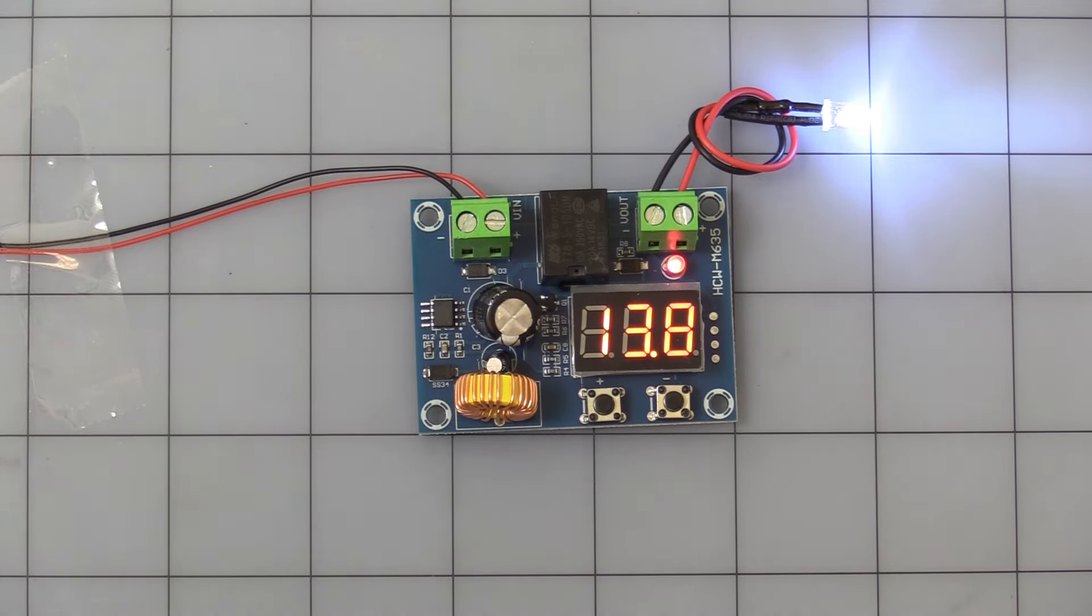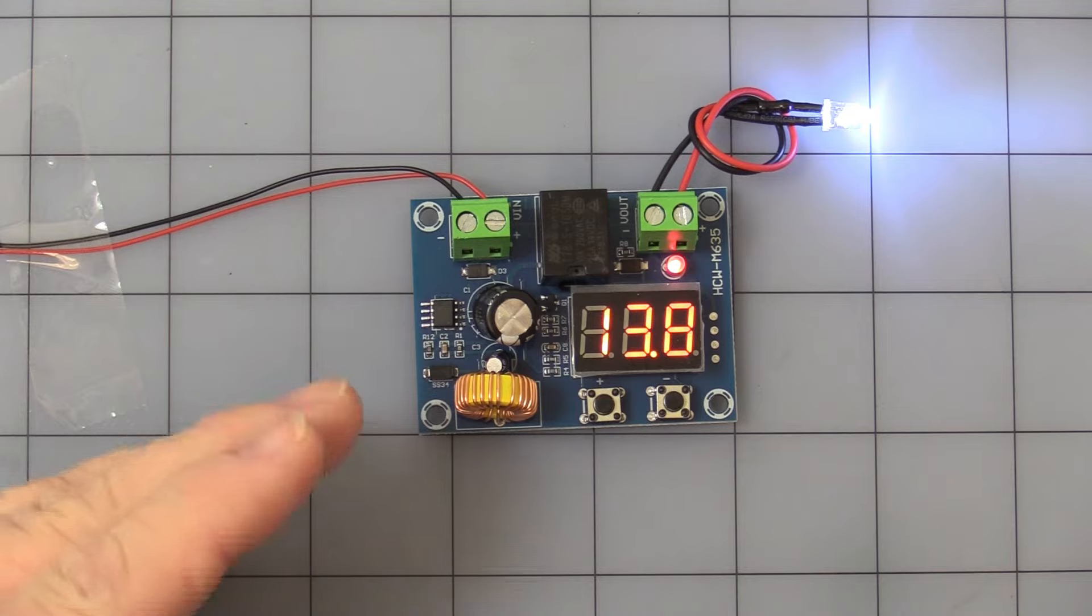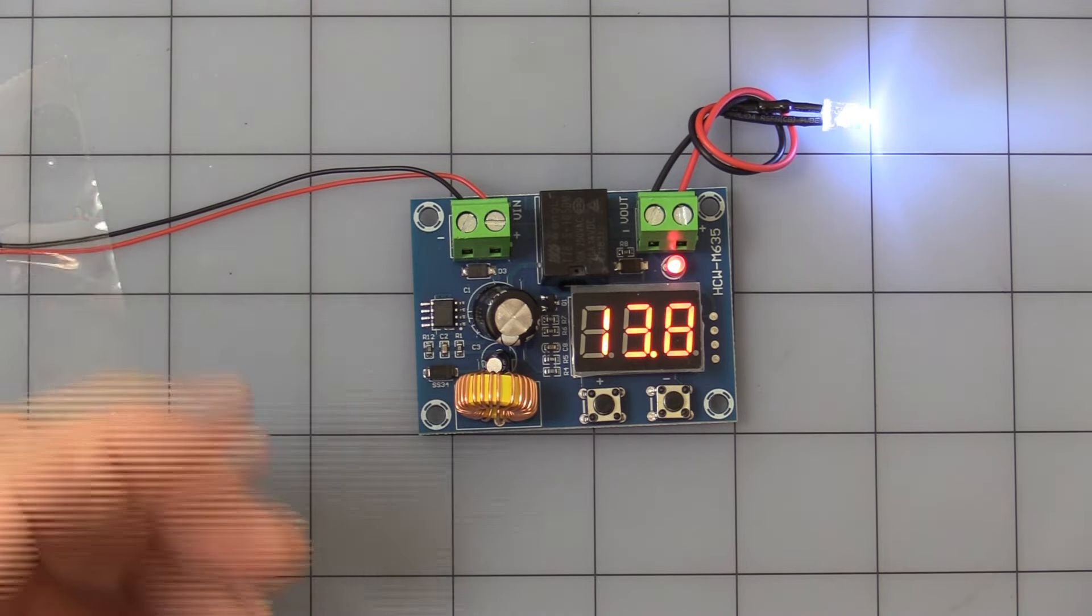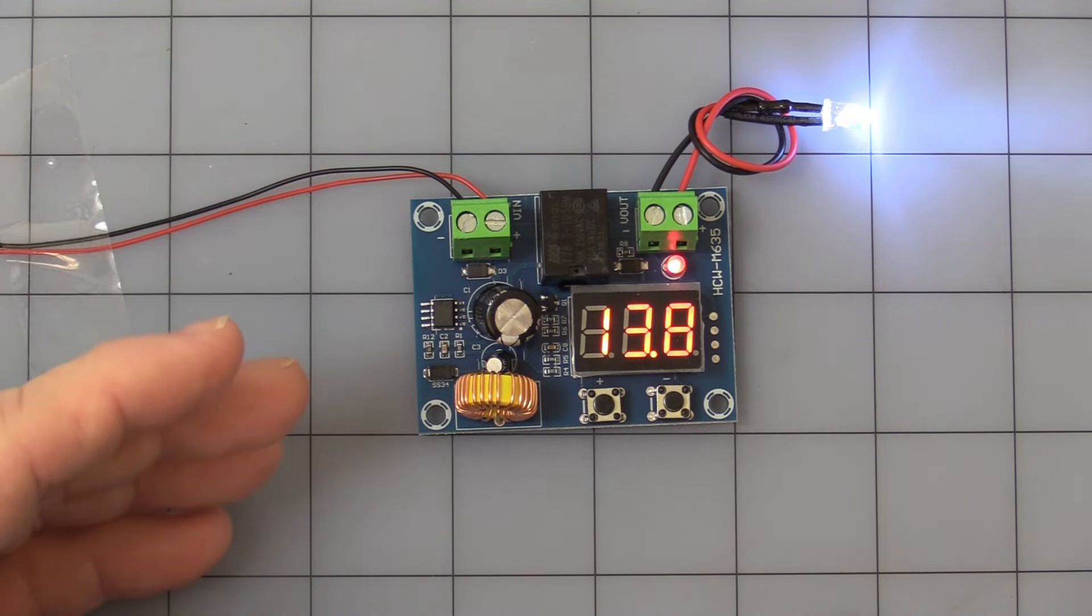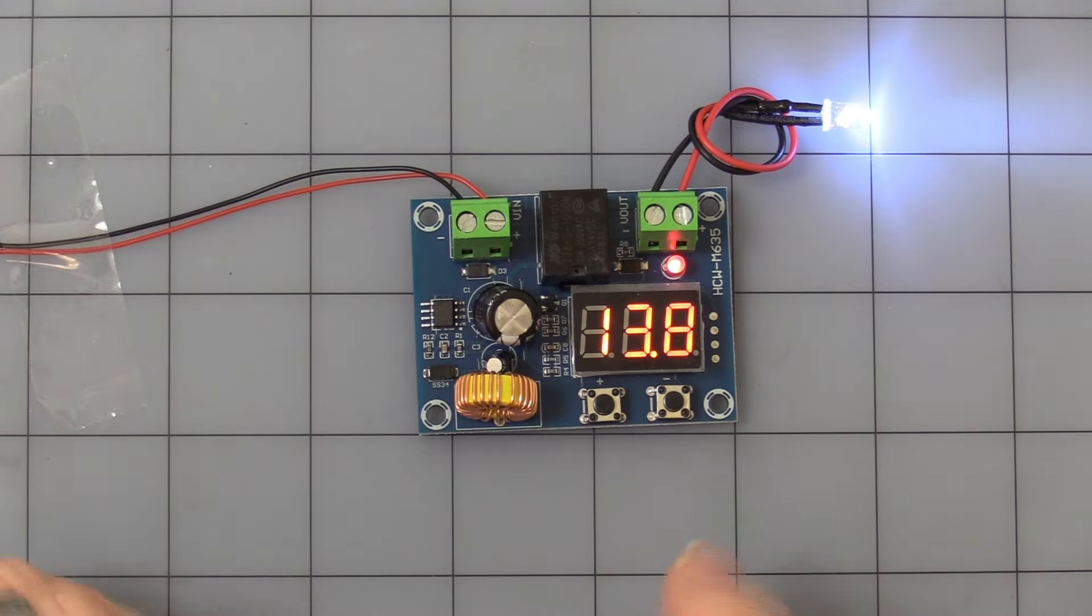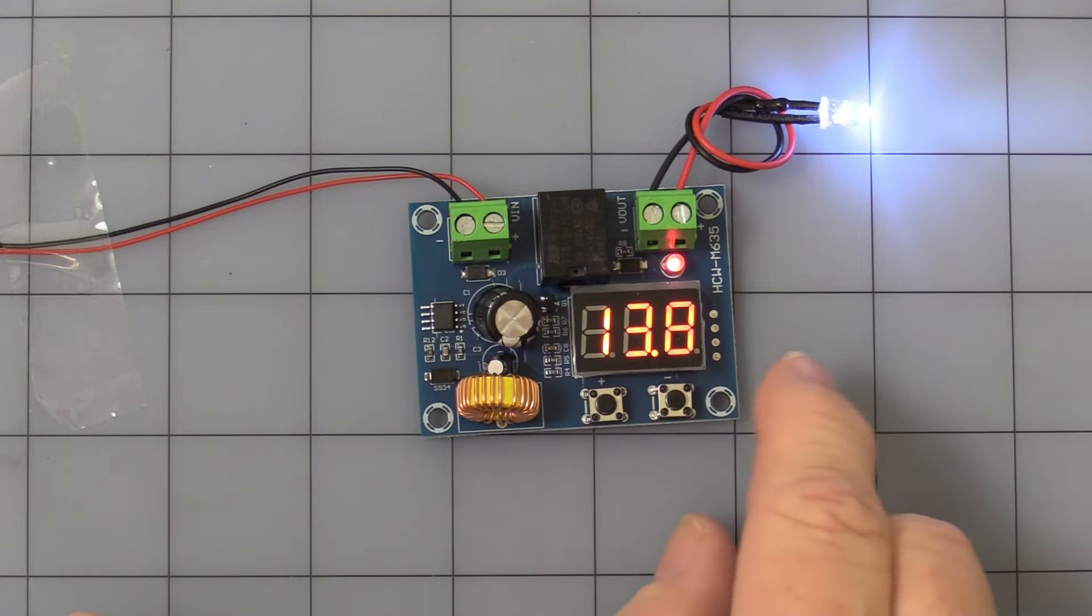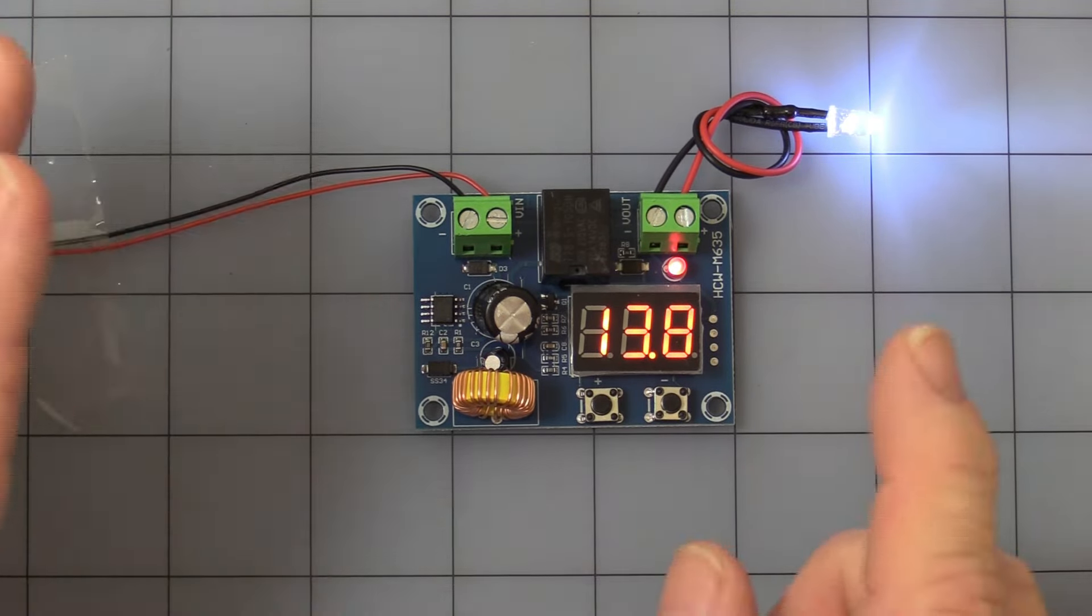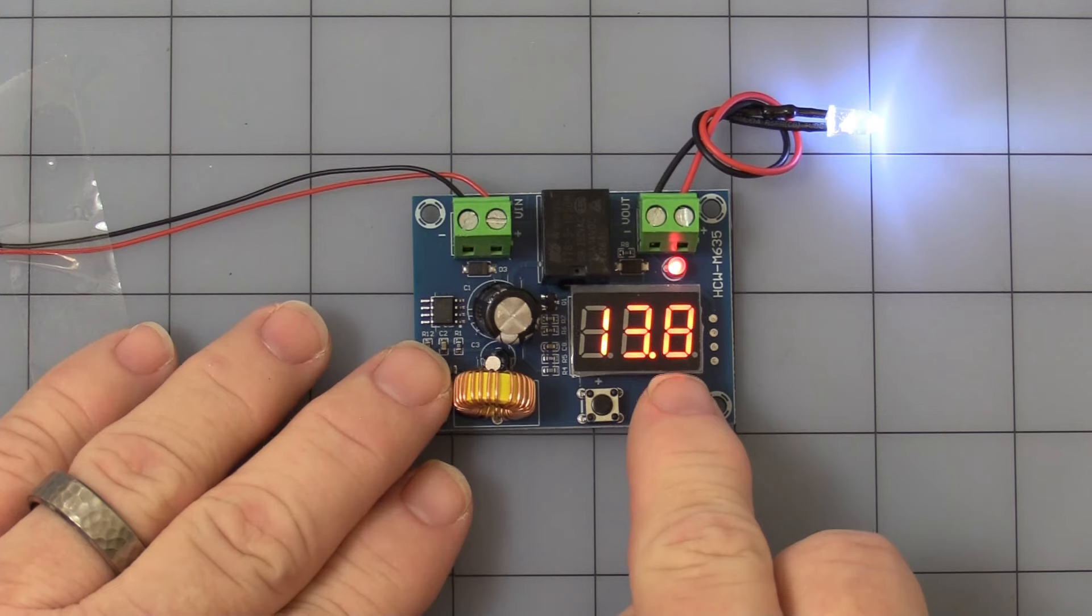And then the last mode is the time mode. Now this is whenever it shuts down, you can have it not turn back on once it gets back to the acceptable range for up to, it says 10 minutes. But I actually played with it and it set, it went up to 60 minutes. But that's what the factory says, 10 minutes. So we're going to stick with 10 minutes.